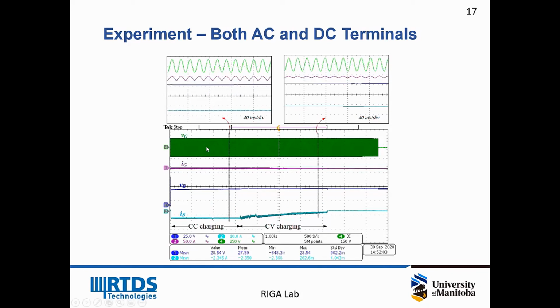If you see the AC side and also the DC side on the same page, you will see that in the very beginning, when the battery was quite empty, the charger provided a constant current charging mode to charge the battery, and the voltage of the battery is increasing, and also for the AC side, the current amplitude here is larger to provide higher power to charge the battery. If you zoom in on this time slot, you will see here is the AC voltage, here is the grid current for the EV charger. But when it reached around 68% SOC, it changed to constant voltage charging mode. That's why the battery current is increasing. And also, zooming into the AC side, the amplitude of the input current is reduced. So here is the full picture to see the whole charging period for the DC and AC side behaviors.